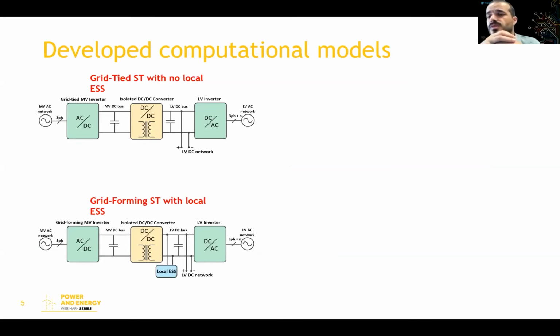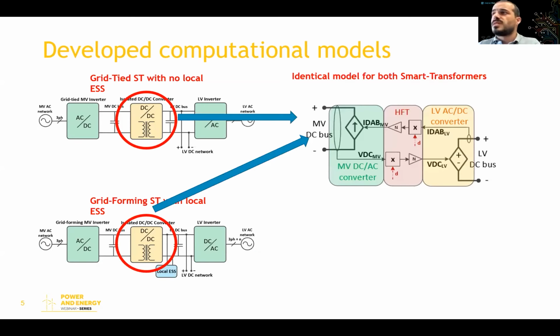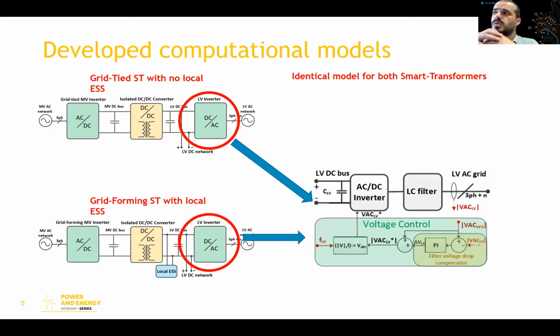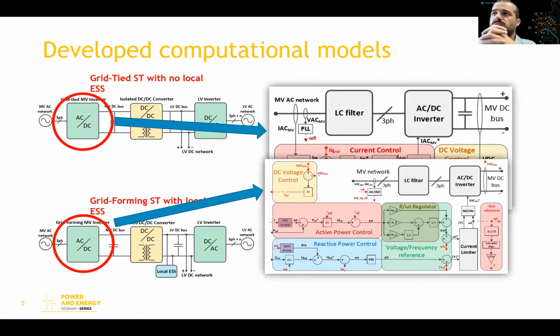In order to do so, some computational models were developed, but we don't have the time here to describe them in detail. So I will focus on the strategies for the fault ride-through, but I will make a brief mention of the models. I would say that the DC-DC stage for both grid-tied and grid-forming smart transformers uses the same model. The same goes for the low voltage inverter in both smart transformers. The main difference is in the medium voltage inverter: in the grid-tied smart transformer, the inverter controls the output current, while in the grid-forming smart transformer, it controls the magnitude and frequency of the output voltage.